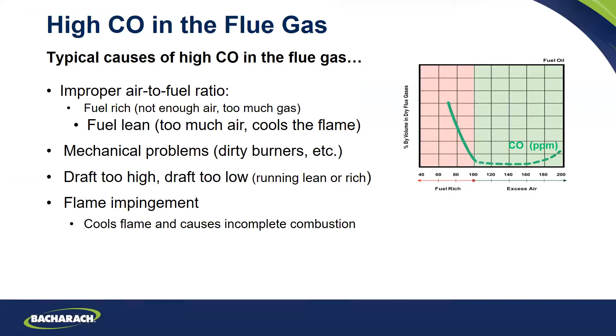Let's check that. You wouldn't check it here because these bring in room air to create draft. A lot of people just drill a hole here and put their probe down through. If you don't want to do that, get a little piece of soft copper, make an L, make a tight connection with the rubber hose so it doesn't suck air. Now you're only reading your CO. If you drill your hole and put the thermocouple probe down there, you're going to read temperature as well.